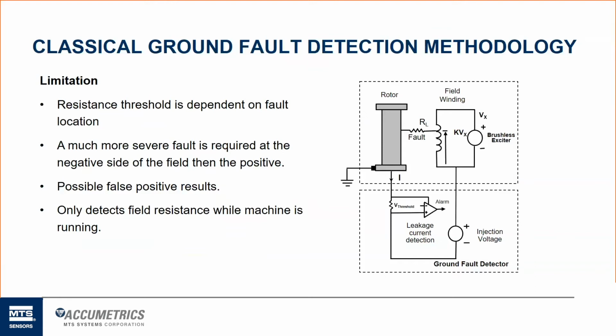So some of the limitations of the classical method: the resistance threshold is dependent on the fault location. It's also dependent on the severity of the fault. So you would need a much more severe fault near the negative side of the field windings and a relatively minor fault near the positive side.